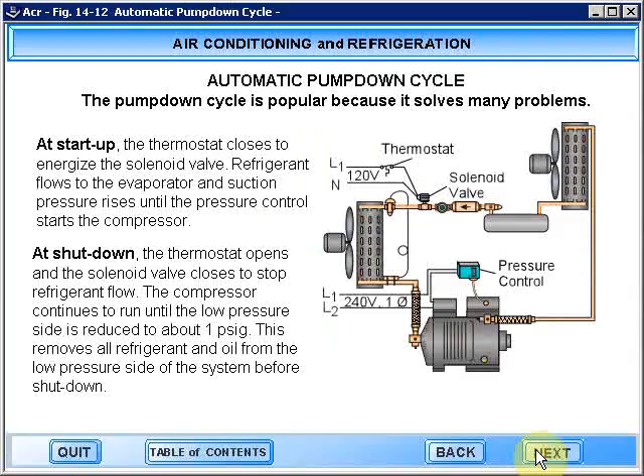The pump down cycle is popular because it solves many problems. At startup, the thermostat closes to energize the solenoid valve. Refrigerant flows to the evaporator and suction pressure rises until the pressure control starts the compressor. At shutdown, the thermostat opens and the solenoid valve closes to stop refrigerant flow. The compressor continues to run until the low pressure side is reduced to about 1 pound gauge. This removes all refrigerant and oil from the low pressure side of the system before shutdown.